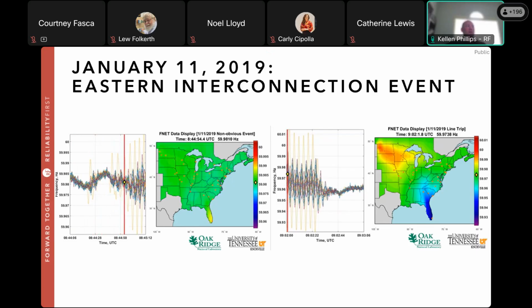That open close was cyclical every 4 seconds and resulted in an oscillation at the perfect frequency to be felt across the entire interconnection. All the way in New England, they saw power swings of about 50 megawatts. The plant itself had oscillations around 200 megawatts peak to peak, for those wondering. The good news, the oscillation ended rather quickly. Operators identified the oscillations quickly using SCADA data and grid monitoring tools and PMU measurements, which Lew will talk about more in a second. It turned out there was failed wiring in the PT cabinet at the plant, and there were faulty valves, the ones that kept opening and closing, meaning the plant was offline for multiple weeks for repairs following this event.